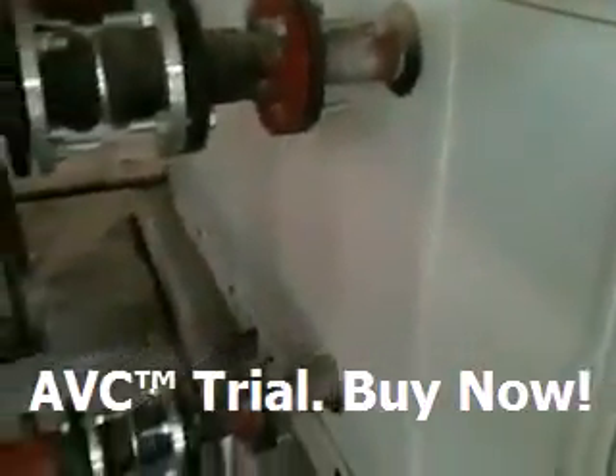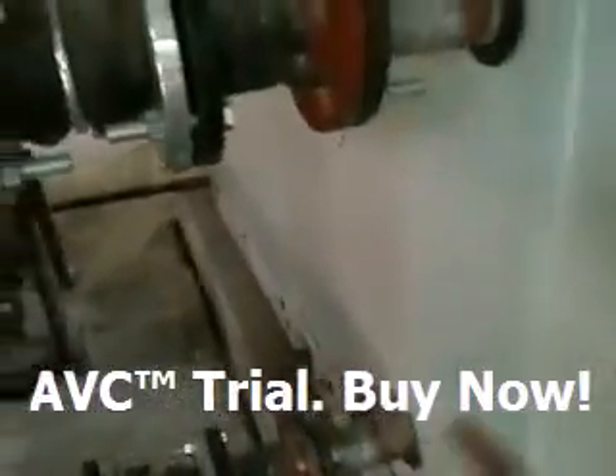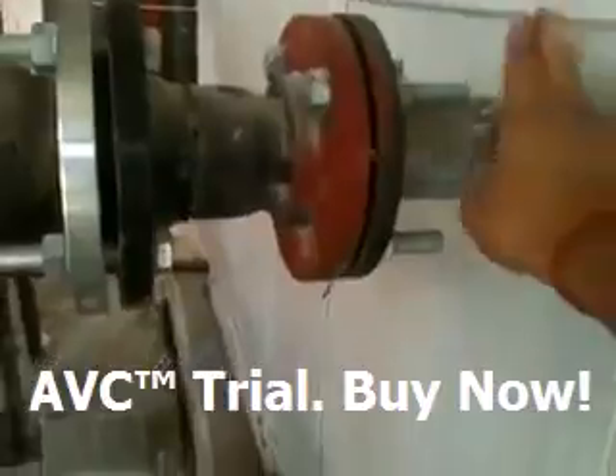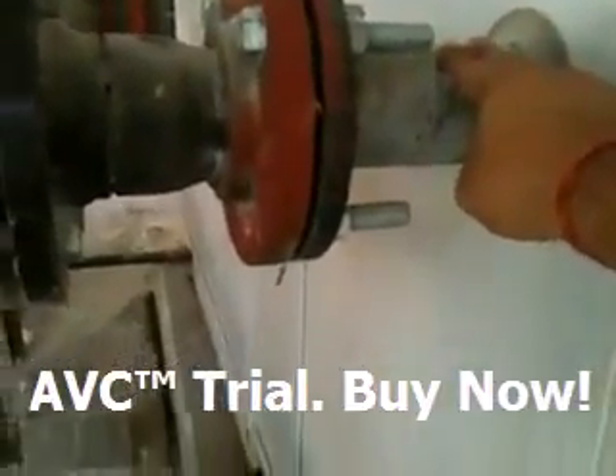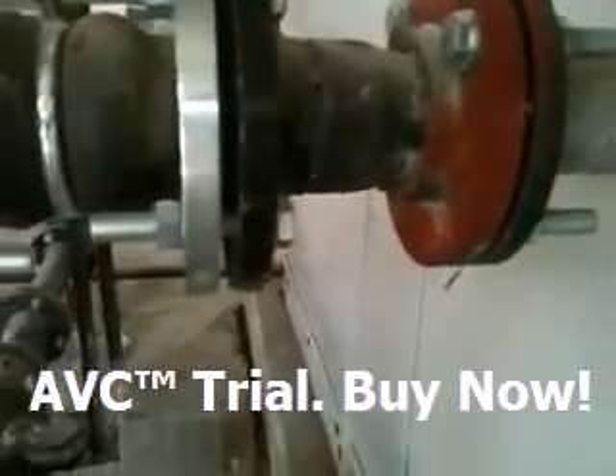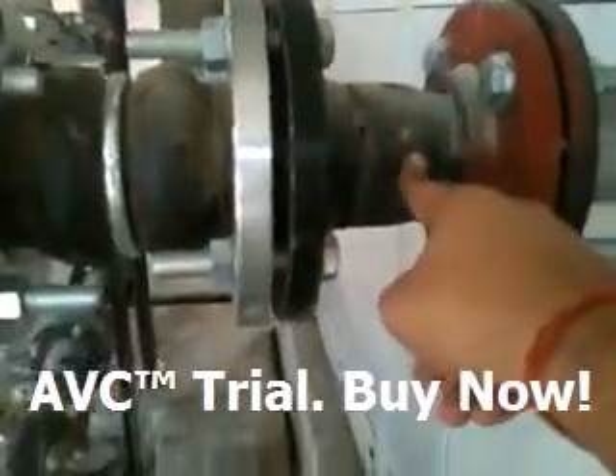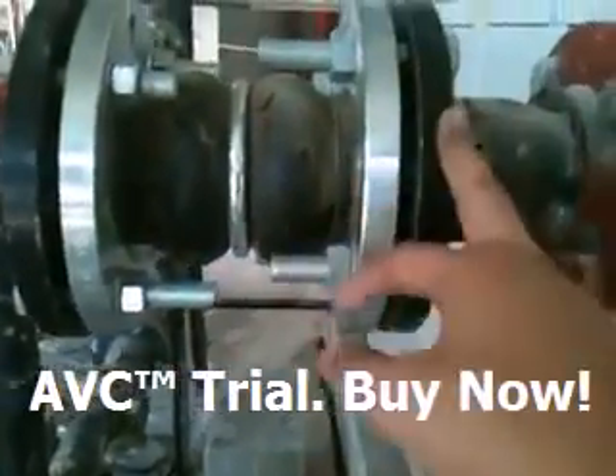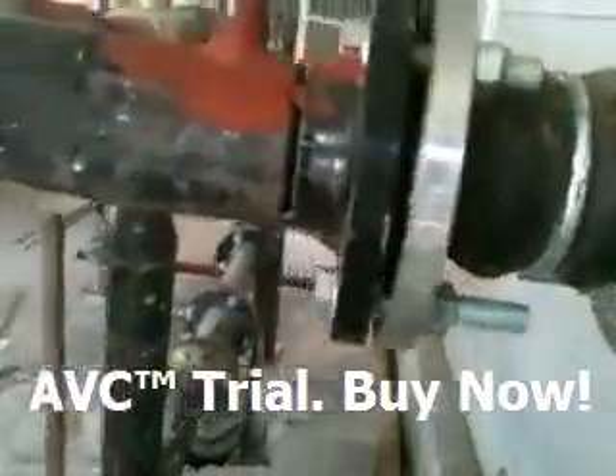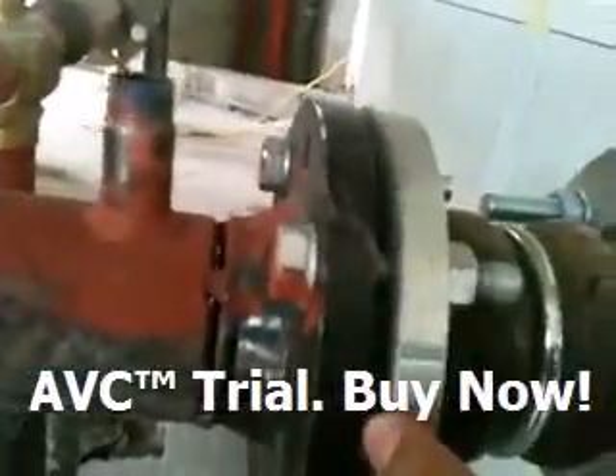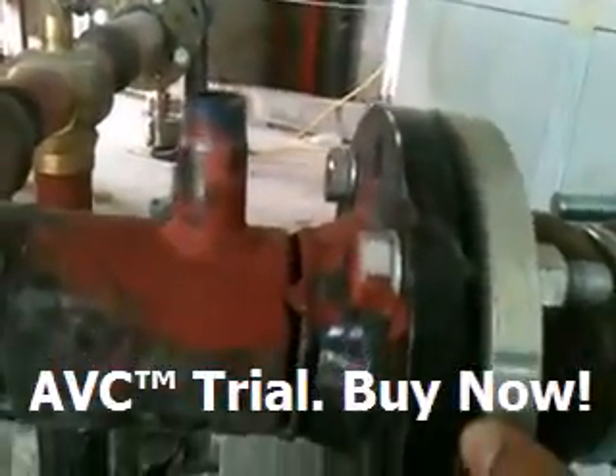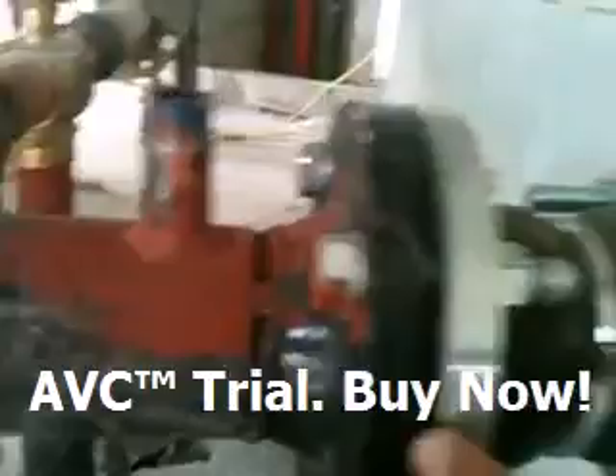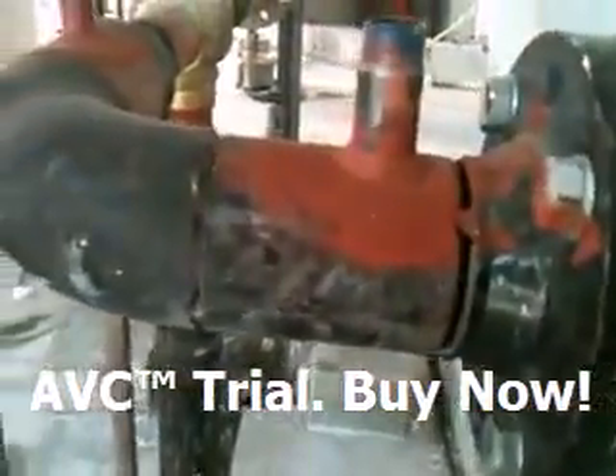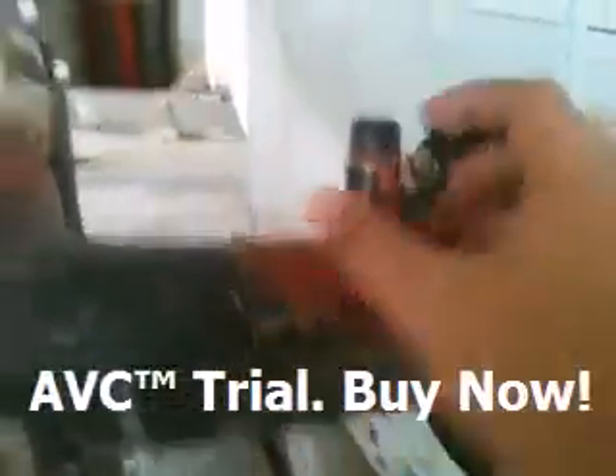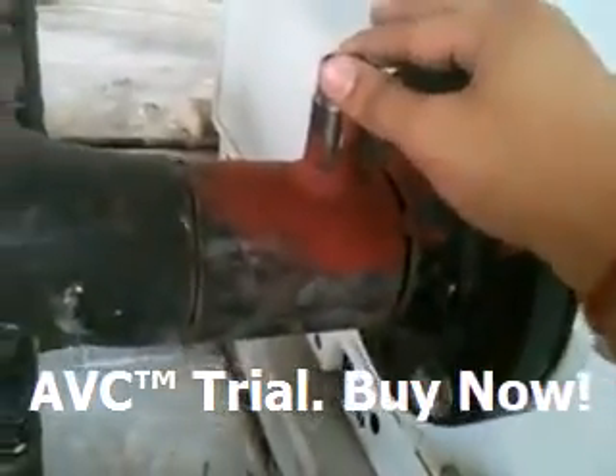Now I'm gonna show you. Now the water which goes into the AHU, now it will return from this line, from this coil. Same, the coil size is 2.5 inch. Then we have flange connection. Then we are putting a reducer again, which makes the line size 3 inches once again. Now here we are putting a flexible. Flexible we put for contraction and expansion of the line, so that it can offer this provision of contraction. And again we have this 3/4 inch connection for thermometer.